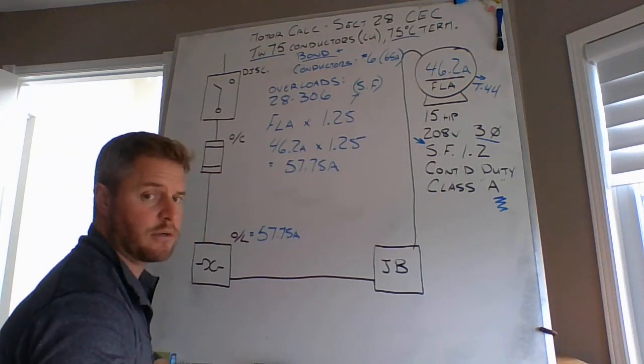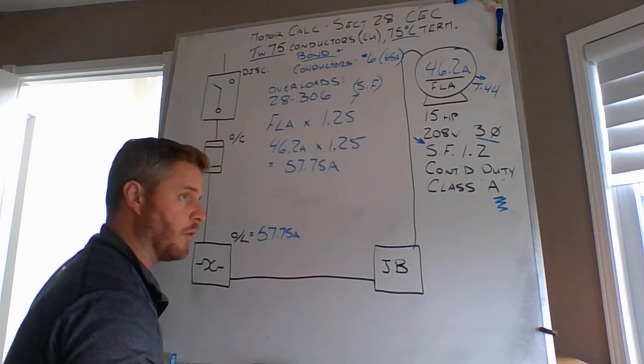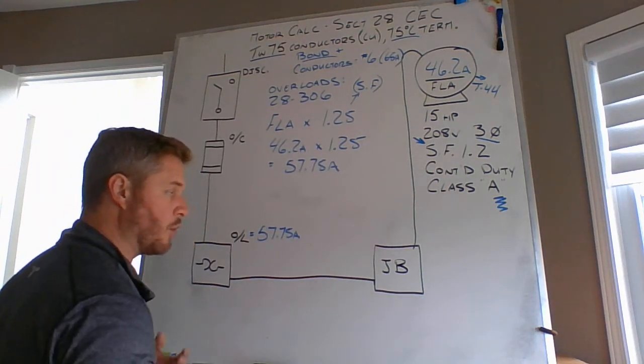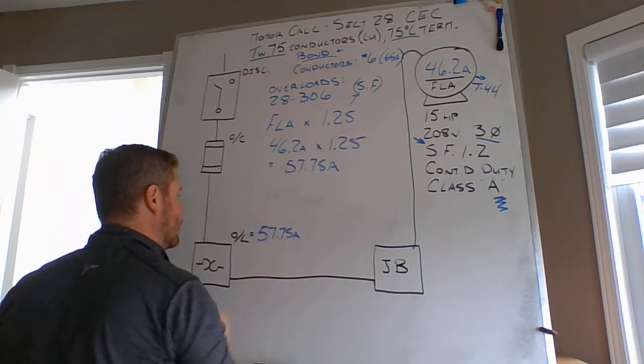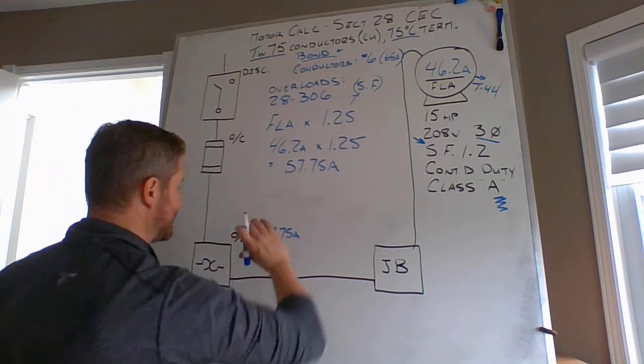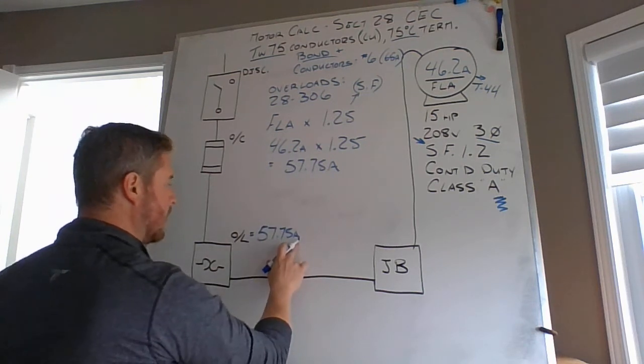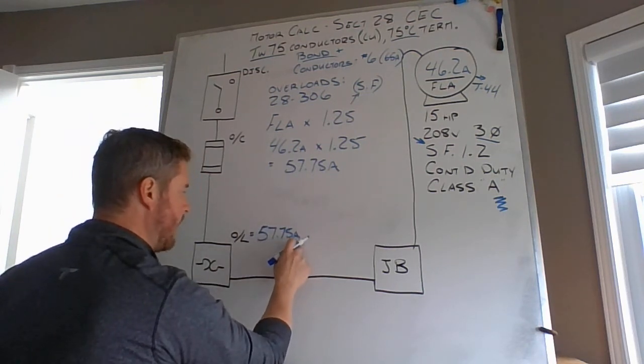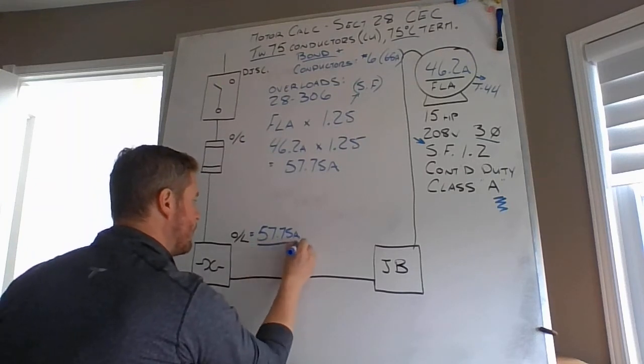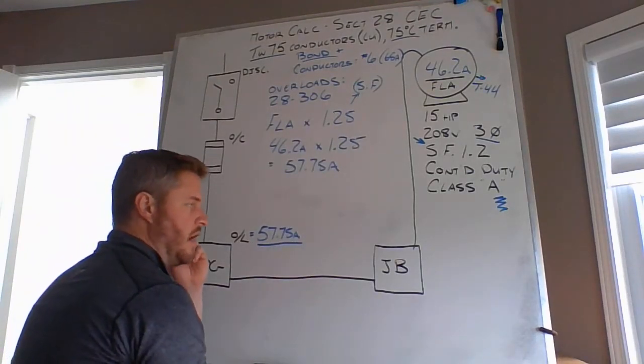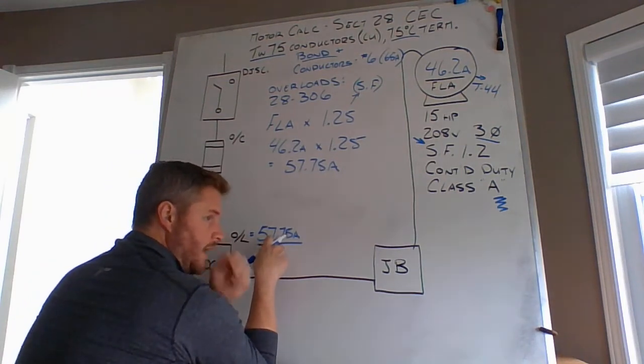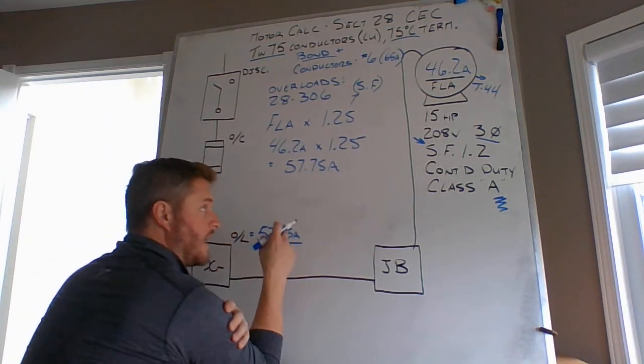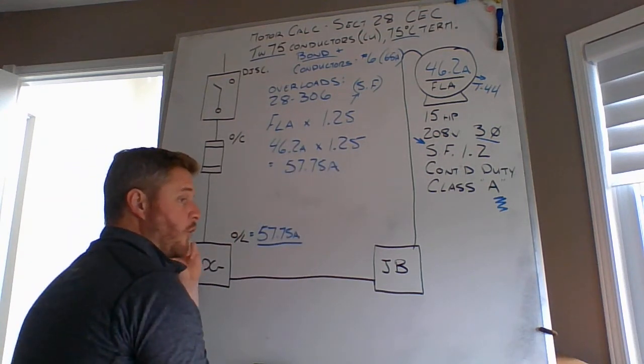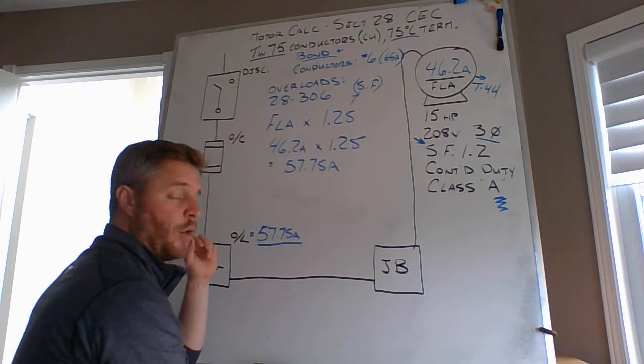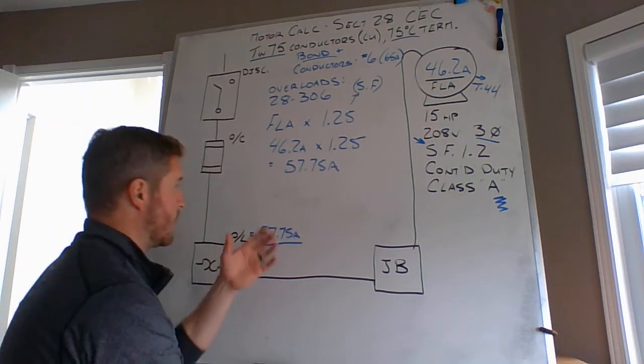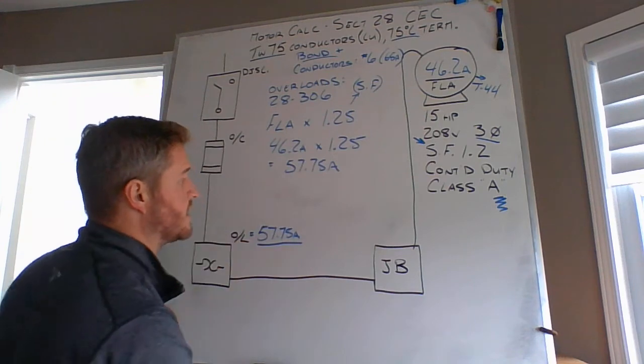The next time that you're in Installation Methods lab, take a look at the IEC starter that you're wiring to perform the task of that motor's operation, and you will see a little blue dial. And you can set that overload to its capable component of 57.75 amps. Now, that 57.75 amps is very interesting for us because it's also the rating or the minimum setting of our conductors to size for this 46.2 amp full load current rating, 15 horse, 208 volt, 3-phase motor with a service factor of 1.2, continuous duty, and a Class A installation.